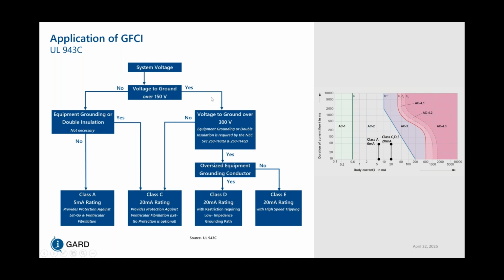Now, if the voltage to ground is over 150 volts and it's within 150 to 300 volts, then you can use a Class C rated device at 20 milliamps. If the voltage to ground is over 300 volts and there's an oversized equipment grounding conductor, you would use a Class D, which is 20 milliamps rated, with a restriction requiring a low impedance grounding path. And then for oversized equipment grounding conductor, if there isn't one, then you would typically use a Class E device, which actually has a higher speed tripping because it's going off a different formula than Classes A, C, and D.